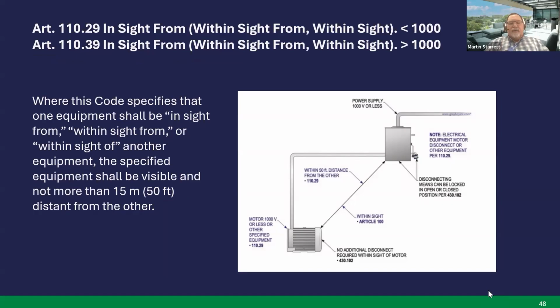Kind of a combination of two articles, 110.29, within sight from, with less than 1,000 volts, and then 110.39 would be greater than 1,000 volts. Where the code specifies that one equipment shall be in sight from, within sight from, or within sight of another equipment, the specified equipment shall be visible and not more than 50-foot distance from the other. So you'll have one article that's for less than 1,000, and then you'll have another article for greater than 1,000. Next slide.